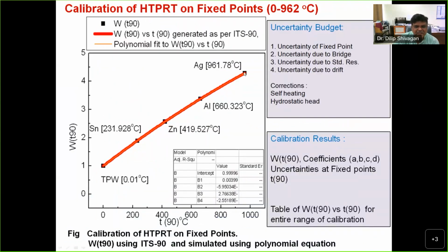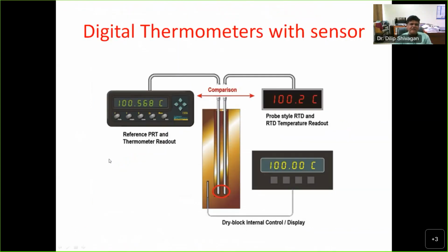And then because we measured at these black dots, say, but we need a temperature at each point, say 1 degree Celsius, then we have to have the interpolation. This SPRT is defined for the interpolation of the temperature between these two. So the uncertainties will be defined based on how many fixed points we have taken into consideration. The more fixed points, the more accurate your measurement will be.